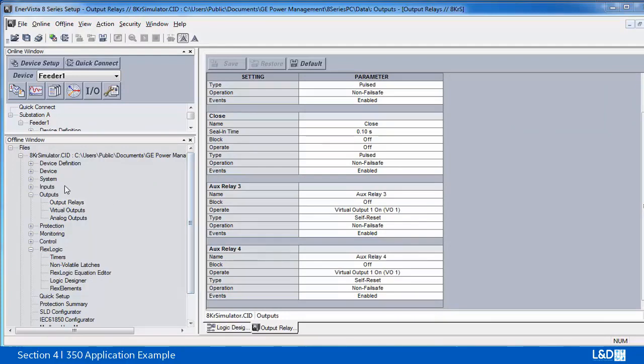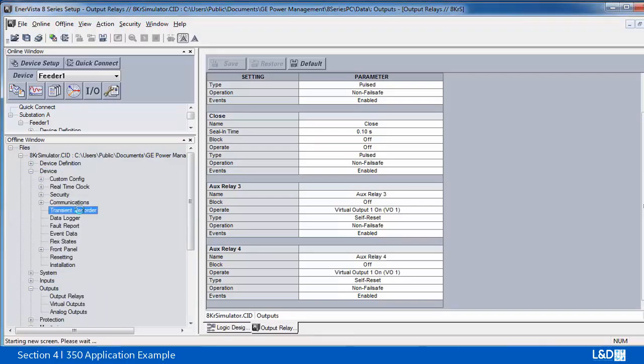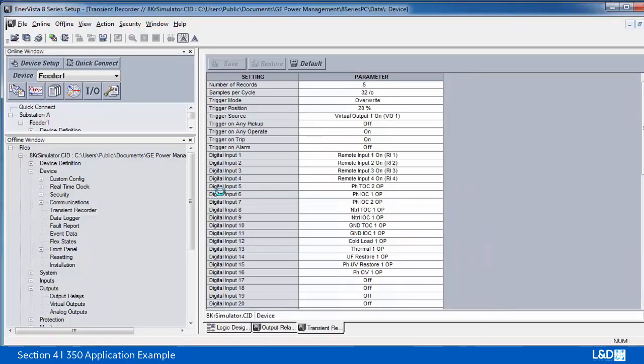And also, in order to check the remote input status, we set the transient recorder for remote inputs 1 and 2. So that's from the breaker: manual close, automatic close, manual trip, and automatic trip. So that's the breaker simulation setup from the 8 series side.